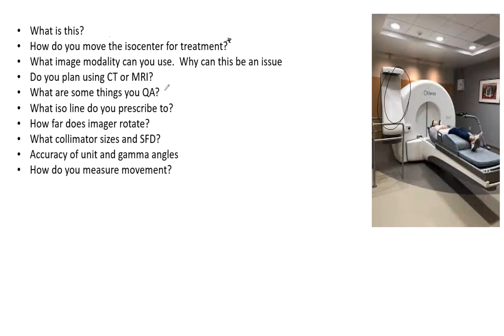What are some things that you would QA? You want to QA the shutter effect, the timer accuracy, and obviously the outputs and the profiles. What iso line do you prescribe to? Typically for the Gamma Knife, we are looking at 50%.